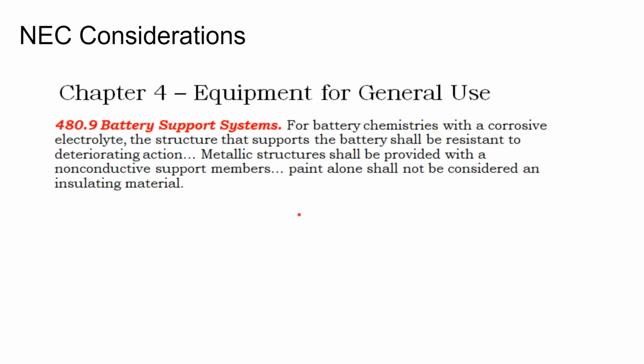Some other requirements: deterioration. Supposedly this hydrogen gas that the batteries emit has a deteriorating effect on metal. Now, I've asked a few installers who have more experience than me on this stuff, and they've never seen metal deteriorating because of their off-grid flooded lead acid battery banks. They say, well, there is some corrosion, but if there is, it's usually around the battery terminals and not surrounding metal because of gas. But that means your metal needs to have some kind of deterioration resistance, whether it be an anodized metal or a painted metal or a plastic coated metal, to be compliant with code.